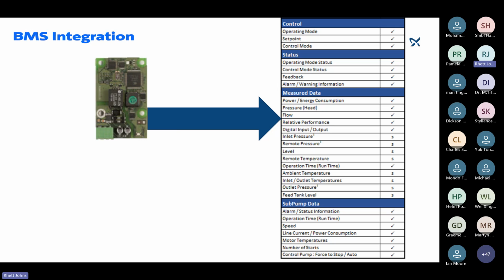So why is this important? Well, when you have access to full data, you can start, in a factory setting, logging these data set points and monitoring the energy consumption and performance of your system. Using that, you can start doing early detection of issues around maintenance. You can start doing early detection of inefficiency, or maybe a system is running outside of the norm, and we want to have a look at it to see if something is operating incorrectly. You can also start doing things like energy consumption monitoring over time.